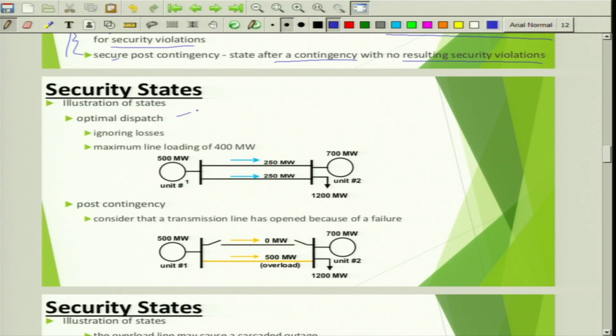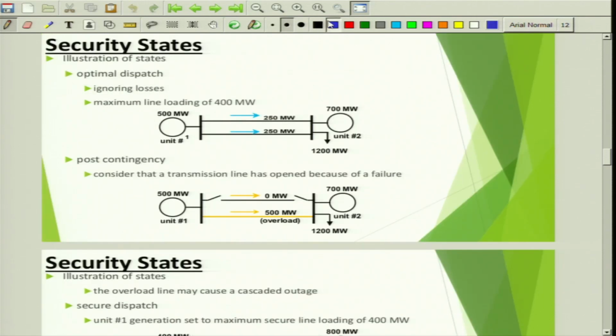First is optimal dispatch. Let us take this as a system. There are 2 generators here, you can see. One is 500 megawatt and the other 700 megawatt, unit 1 and unit 2, and there are 2 lines. Each has a maximum line loading capacity of 400 megawatt, right, and there is a load connected at bus 2 which is 1200 megawatt. Now what is happening? There is 700 megawatt being supplied by unit 2, and the remaining 500 megawatt is supplied by unit 1. There are 2 lines, so it is divided across them, 250 each. Each line loading capacity is 400 megawatt, right. So there is no violation here, optimal dispatch is happening.